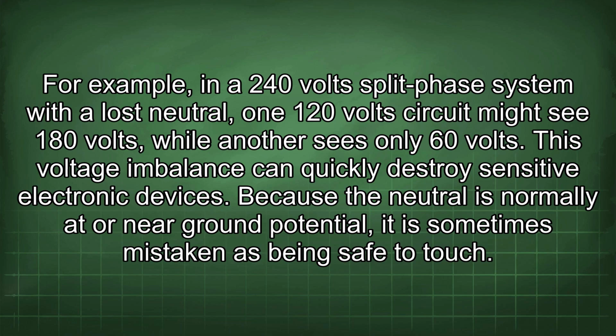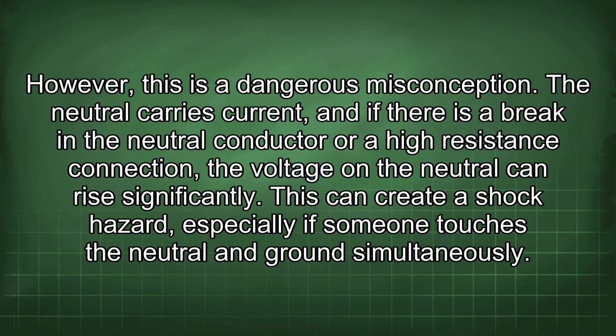Because the neutral is normally at or near ground potential, it is sometimes mistaken as being safe to touch. However, this is a dangerous misconception. The neutral carries current, and if there is a break in the neutral conductor or a high resistance connection, the voltage on the neutral can rise significantly. This can create a shock hazard, especially if someone touches the neutral and ground simultaneously.